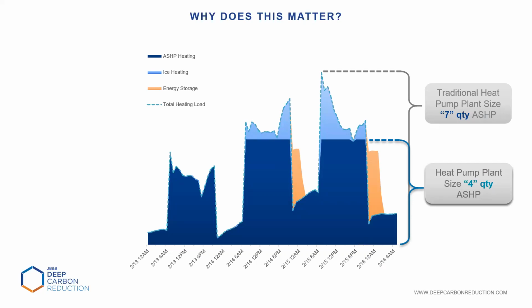The key differentiator for why ice heating is important, especially in the New York City market, is the ability to reduce your heat pump quantities and capacities. A typical designer does his load calculation, picks the lowest temperature day per ASHRAE, reduces plug loads, maximizes occupancy, and says he needs 7 heat pumps to meet that peak condition, maybe adding safety factors for worst case. But when you deploy the ice heating solution, you can reduce your heat pump plant down to, in this theoretical condition, 4 units — about a 40% reduction in equipment, saving a lot of roof space.